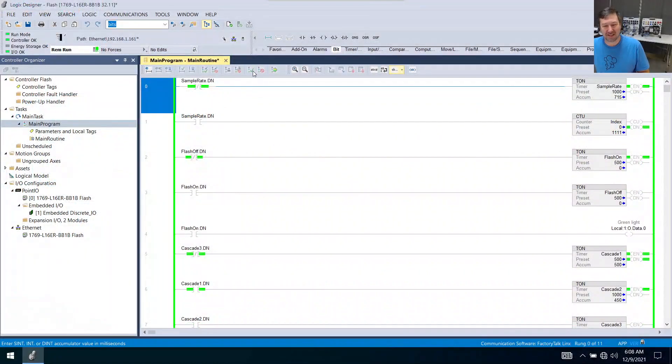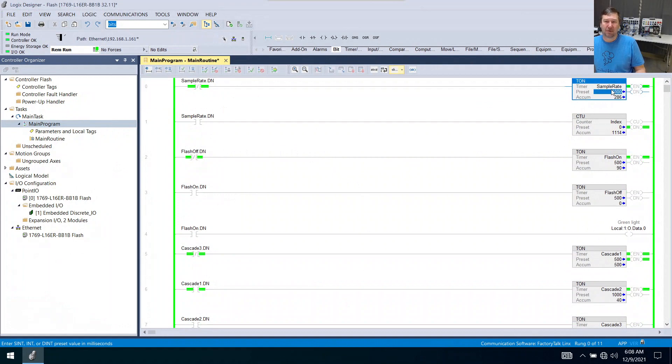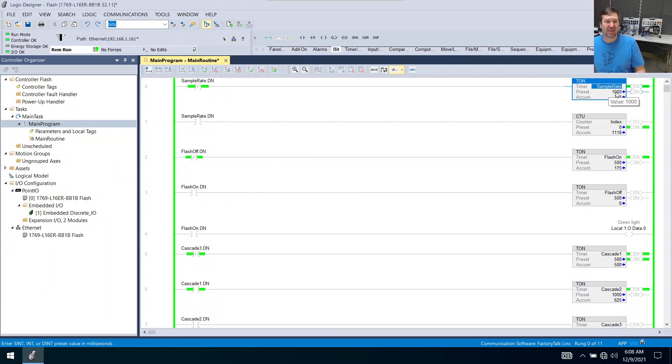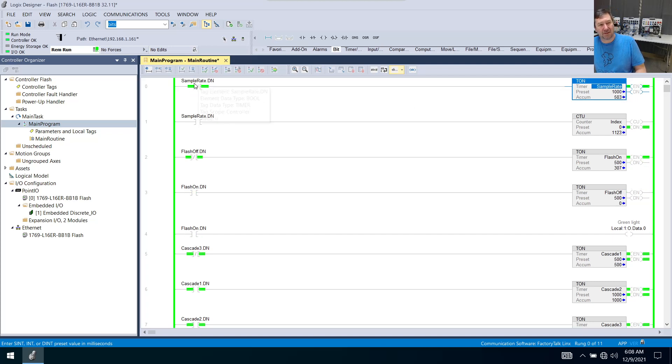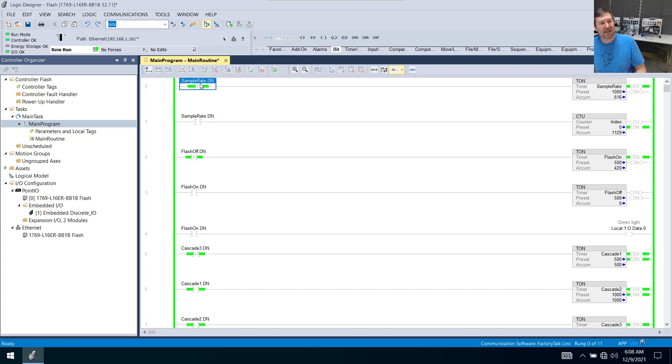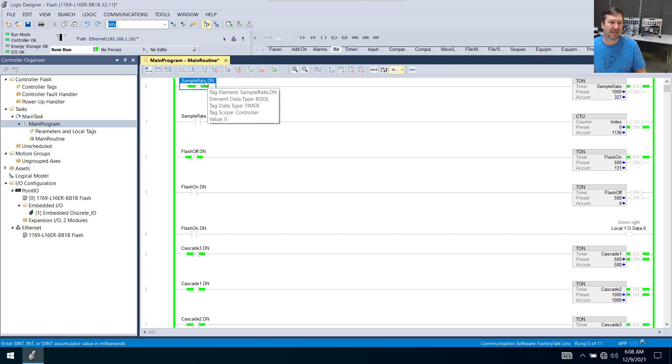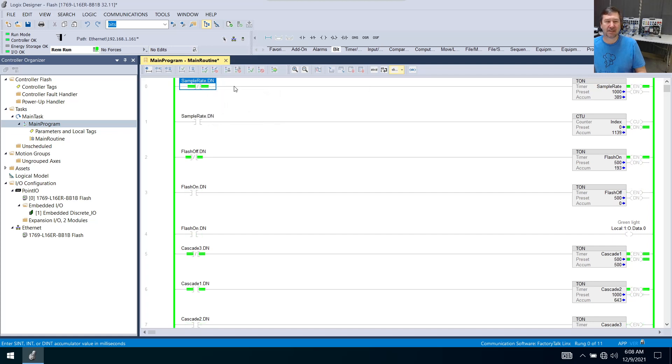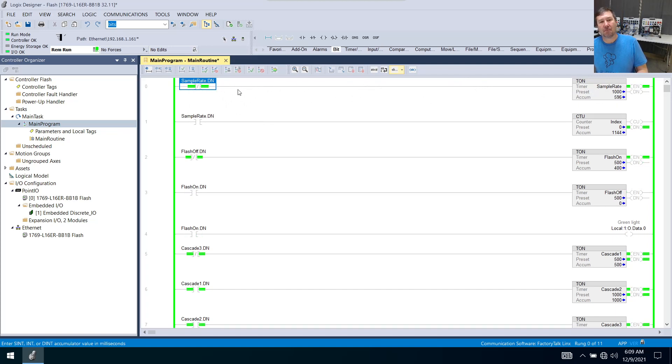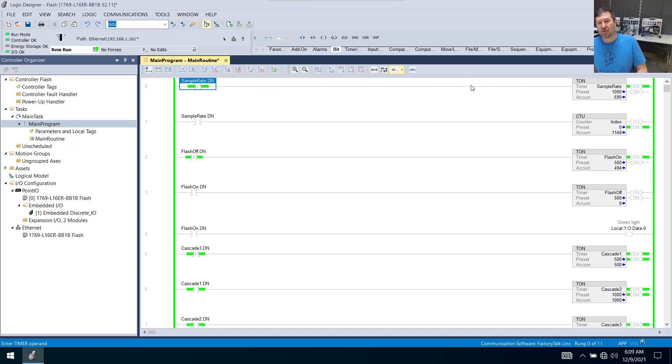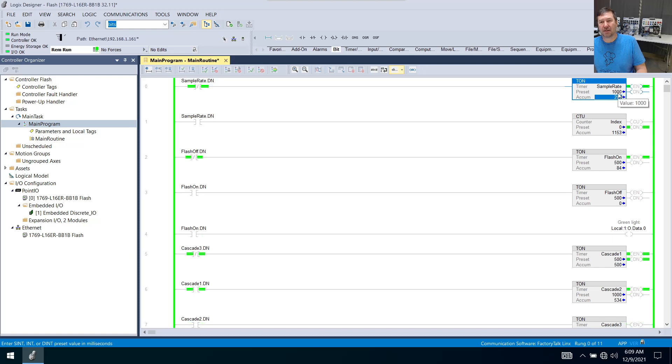So let's look at this first one right here. If we have sample rate and this is a timer, it's a TON, and we have a preset of 1000. Now the instruction preceding it is an examine off, which if you've watched many of our videos, that means go look for a zero at samplerate.dn. So our first thing we have to understand is when is samplerate.dn a zero and when is it a one? Samplerate.dn is going to be a one when the instructions preceding it are true and the accumulated value is greater than or equal to the preset.